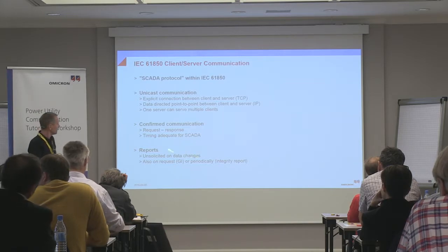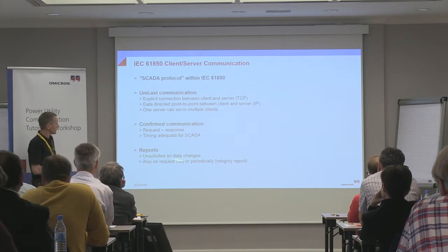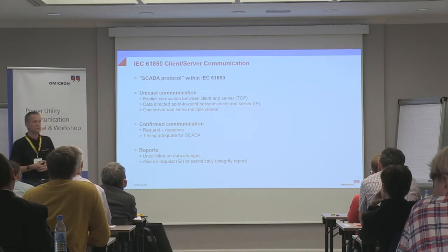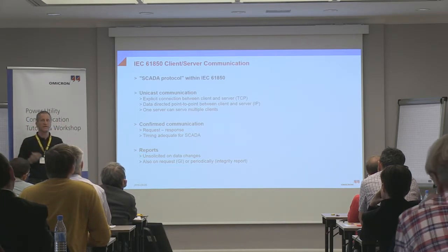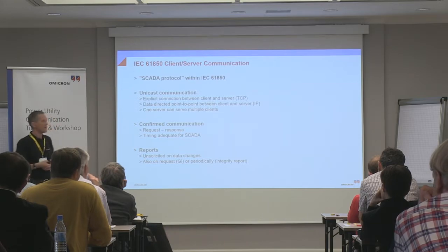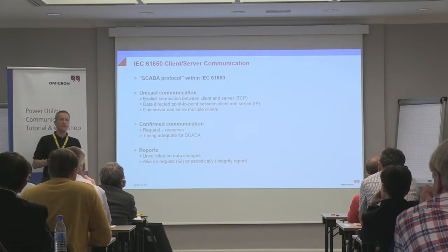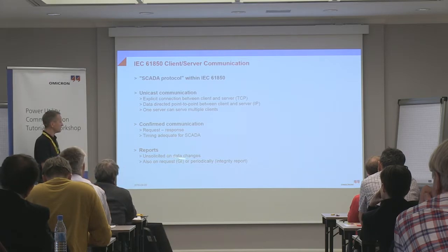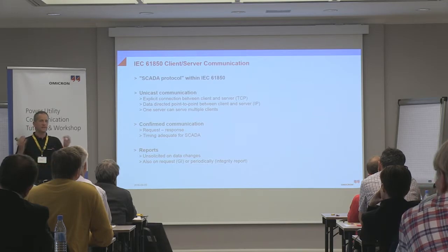Here we have something different. We have these so-called unsolicited reports, spontaneous reports. When such a client-server communication is set up, the client can subscribe to a report, and whenever a so-called trigger condition is met, which is typically a data change, then the server will send this report to the control center.